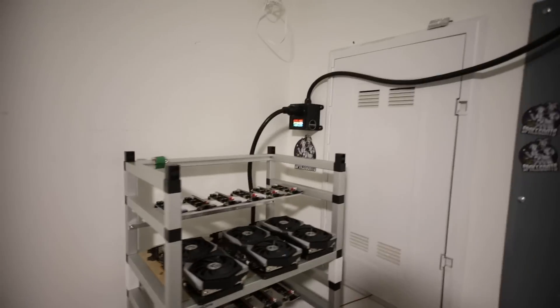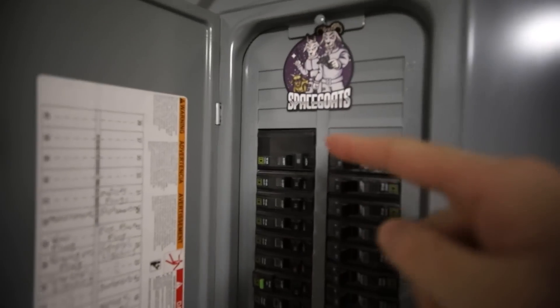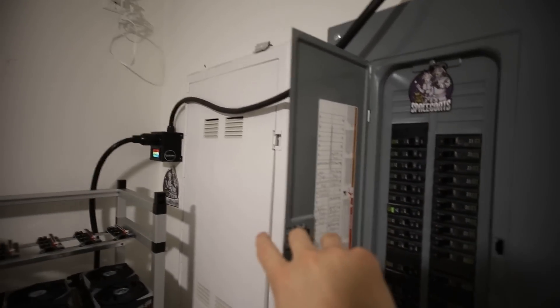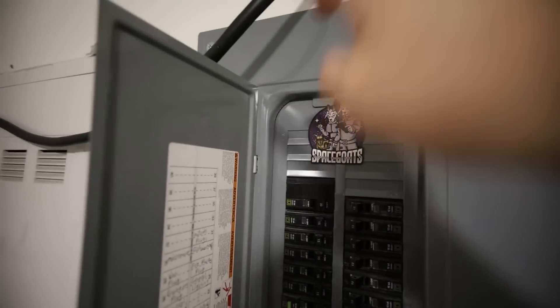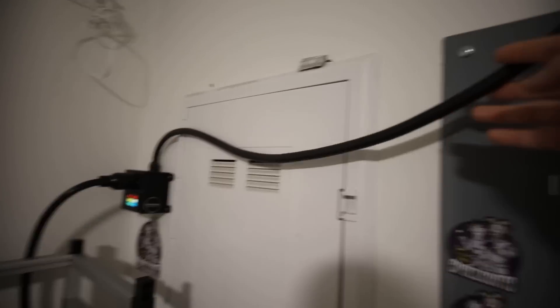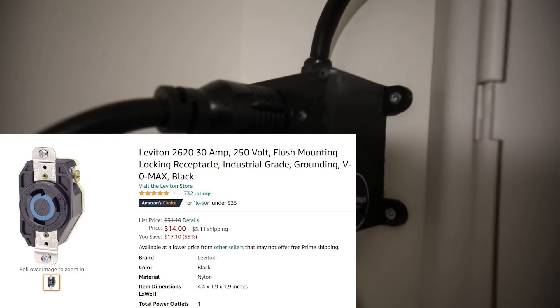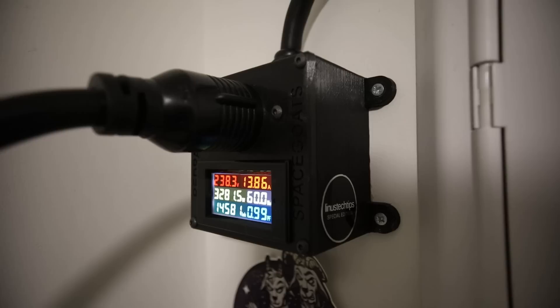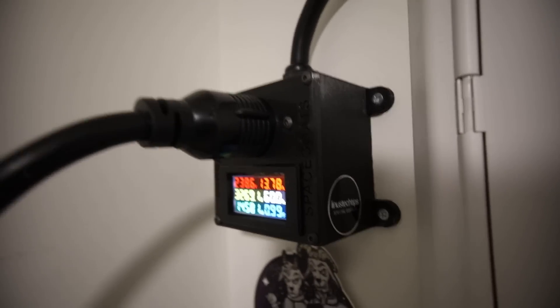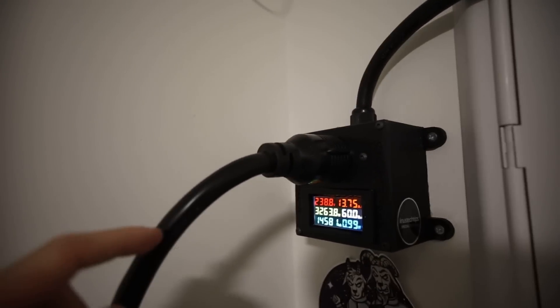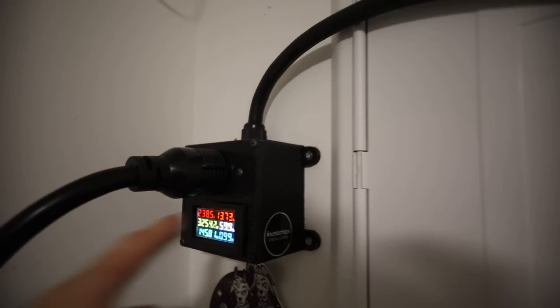So how I'm powering my S19J Pro. So it is being run into a main panel first out of a 240 volt 30 amp breaker. And just before I explain everything else, I want to have a disclaimer. Make sure you have a proper electrician wire this all. And so going into this 30 amp 240 volt breaker is 10 gauge wiring coming from this cable here going into a 30 amp receptacle. 240 volt 30 amp receptacle.